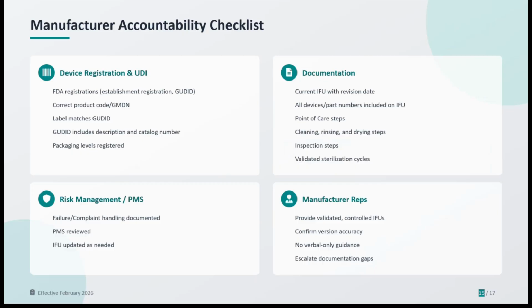So given what we've discussed so far, what should you expect from a compliant manufacturer? For devices, they should be correctly registered in the FDA systems, including the establishment registration and GUDID, with an accurate device identifier. Packaging levels, descriptions, labels, and GUDID data should match.